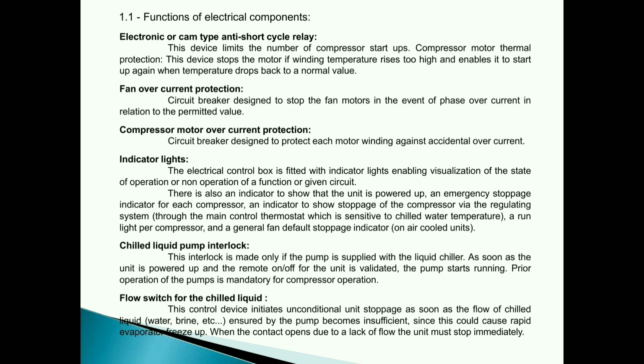Chilled liquid pump interlock. This interlock is made only if the pump is supplied with the liquid chiller. As soon as the unit is powered up and the remote on-off for the unit is validated, the pump starts running. Prior operation of the pumps is mandatory for compressor operation.